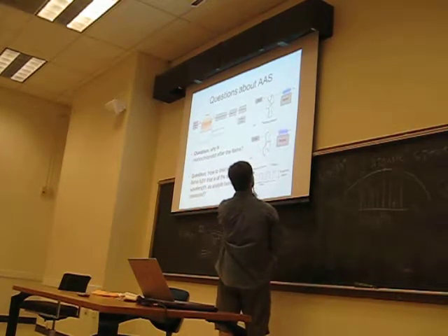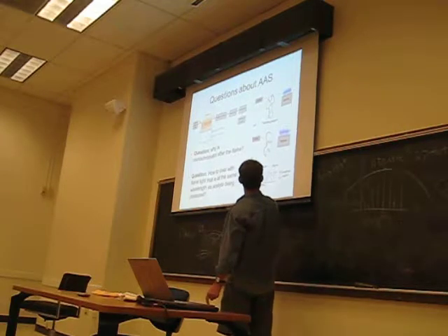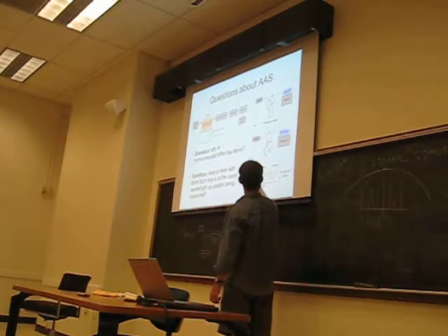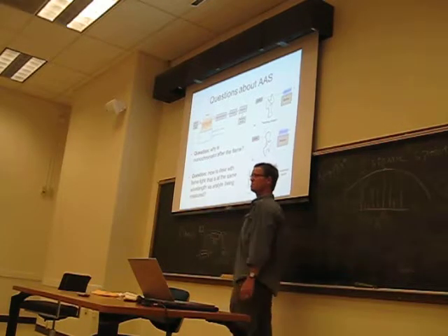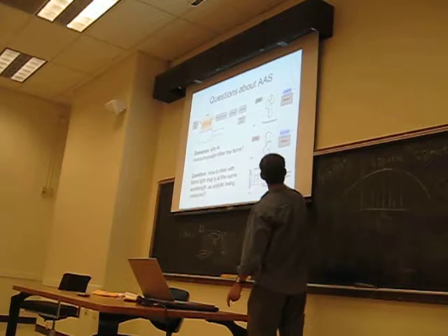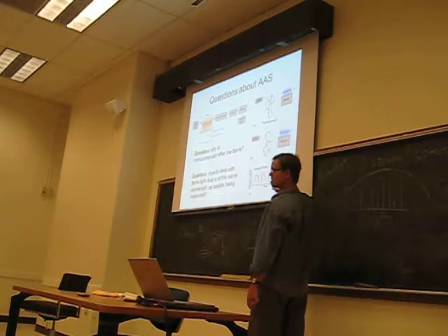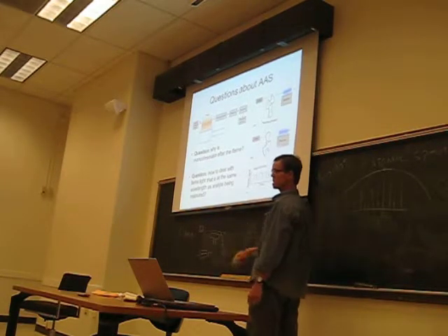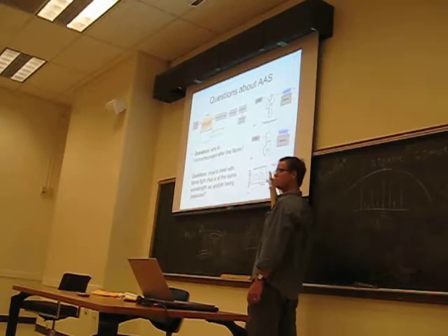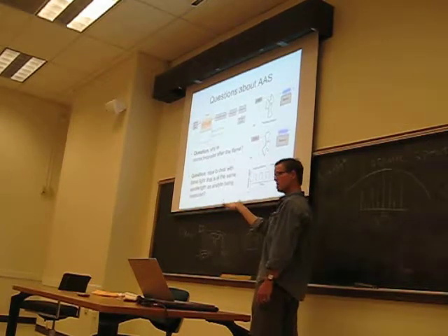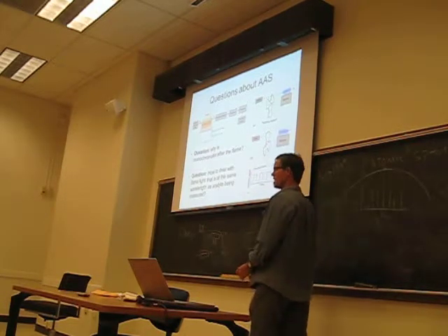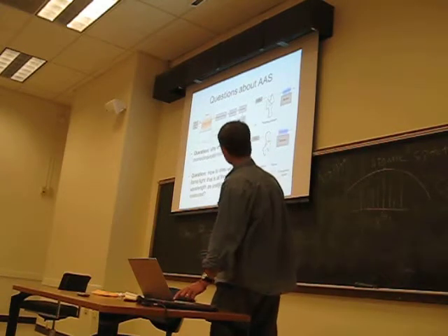It's measuring photons when the lamp is being blocked, so this is only the flame, and then it's measuring all of them, and it gets this square wave signal that can distinguish the difference between photons generated by the flame versus the hollow cathode line, which is specific to copper. The instrument electronics handle that and generate an absorbance signal for us that already corrects for that. So these guys have thought of everything. Okay.